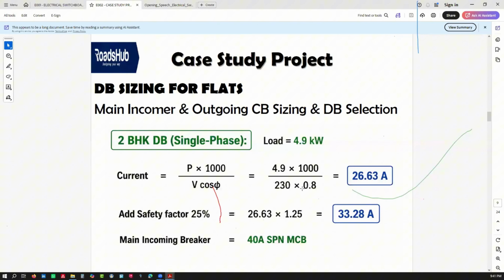That's why we said that when you're doing design, we have assumptions, and those assumptions need to be stated. Like this power factor is an assumed power factor. We do that because realistically you wouldn't get a system that is more efficient, even in a building, because we have motors, lifts, pumps, and all those systems that have a reactive component. So we use 0.8 for a design. But again, to get the main breaker value, you need to add a safety margin of 25%. Actually, that's an average of 20 to 30 in between. So you add that extra value, and you get 33.28.